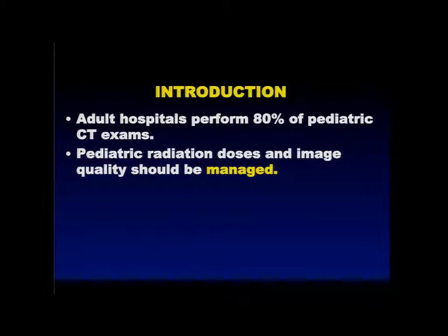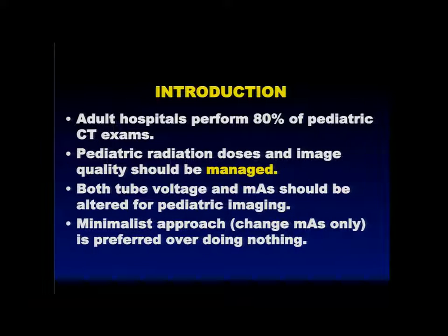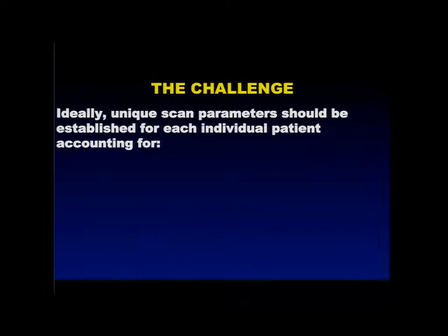Obviously, we should manage dose and image quality for pediatric exams, and also for adult exams. You're going to get a pediatric bent from me because I've been working in pediatric hospitals for 32 years. Both the X-ray tube voltage and the MAS should be altered for pediatric imaging. A minimalist approach where you change only the MAS to reduce dose for kids is preferred over doing nothing, but ideally you should also reduce the KVP.